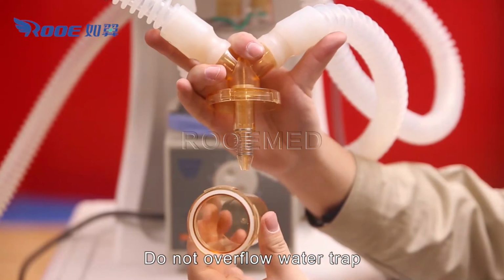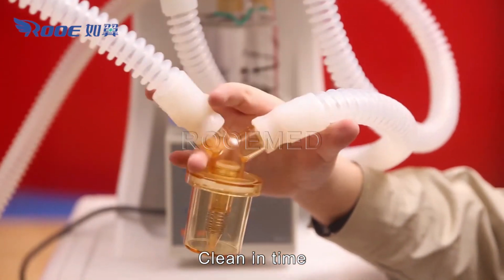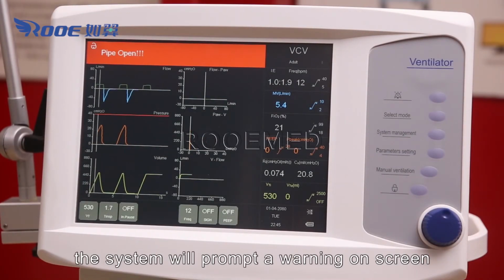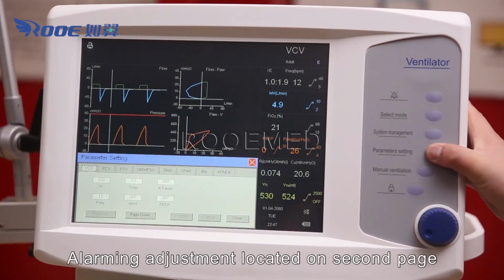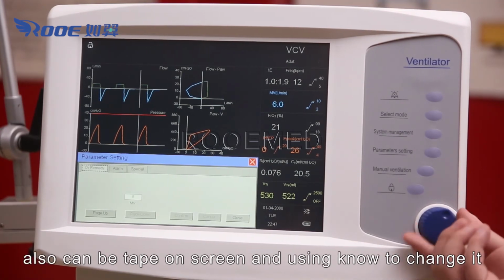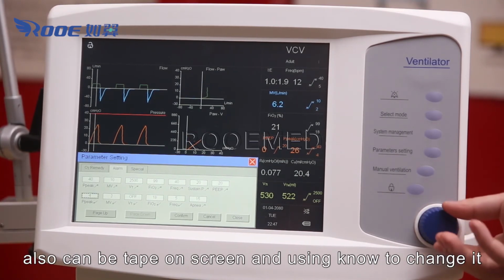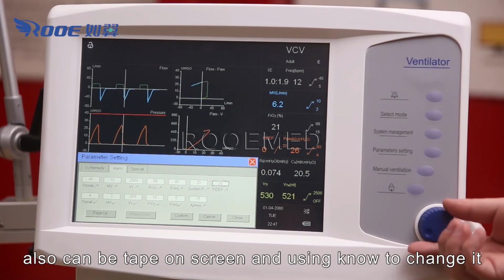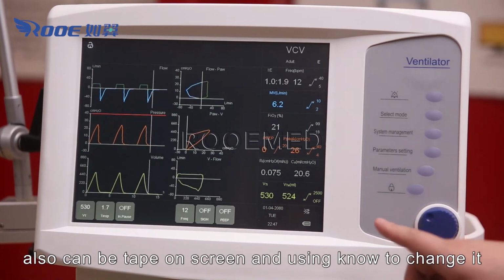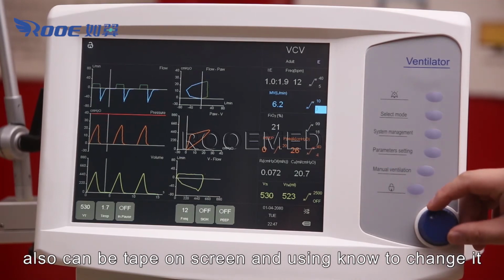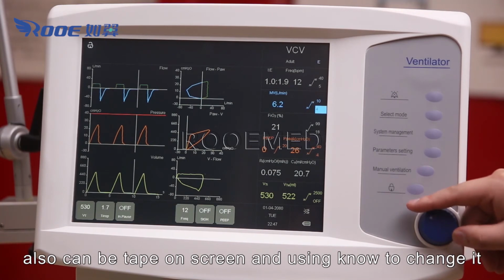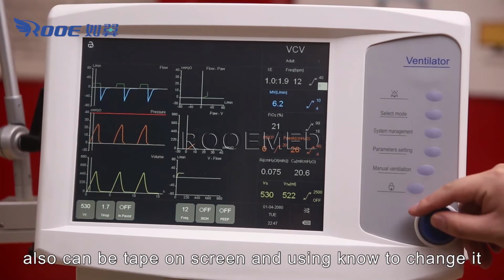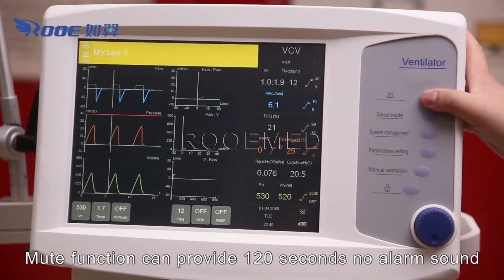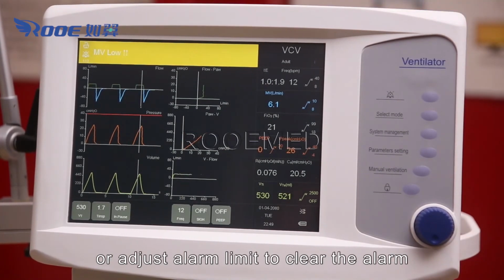Alarms and cautions. Do not overflow the water trap. Clean in time. When the breathing circuit is disconnected, the system will prompt a warning on screen. Alarm adjustment is located on the second page. It can also be tapped on screen, using the knob to change it. The mute function can provide 120 seconds of no alarm sound, or adjust the alarm limit to clear the alarm.